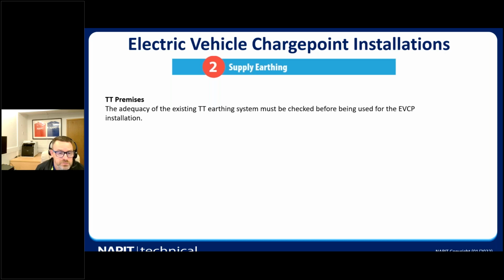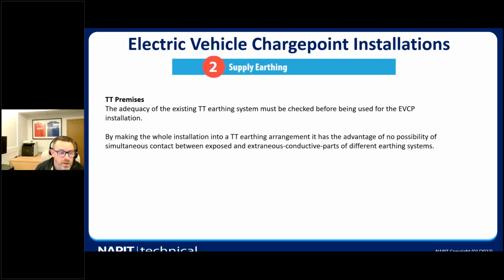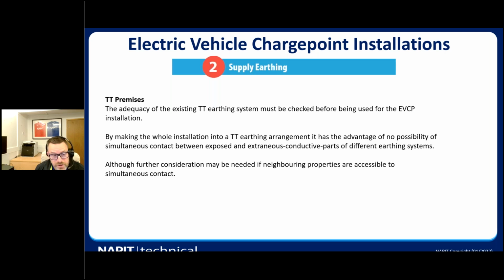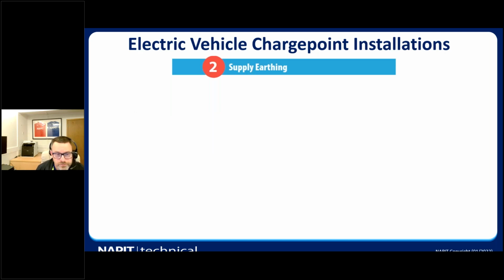TT premises, the adequacy of the TT system must be checked before any EVCP is installed. Making the whole installation TT has the advantage of no possibility of simultaneous contact between exposed and extraneous conductive parts of the different earthing systems. But we need to consider with TT systems where there are neighbouring properties, and is there simultaneous contact between those parts.